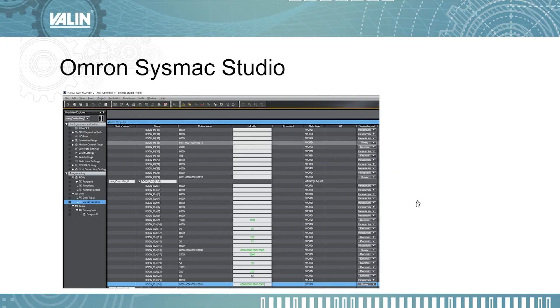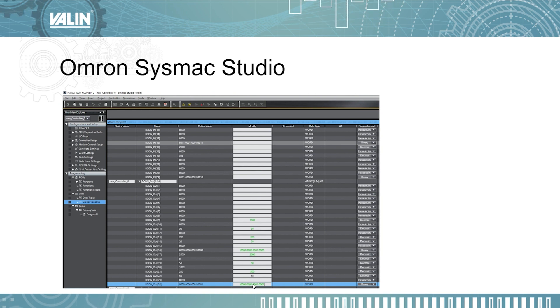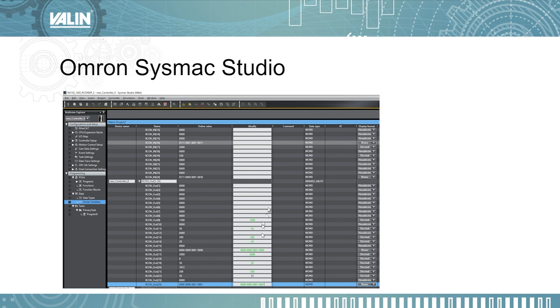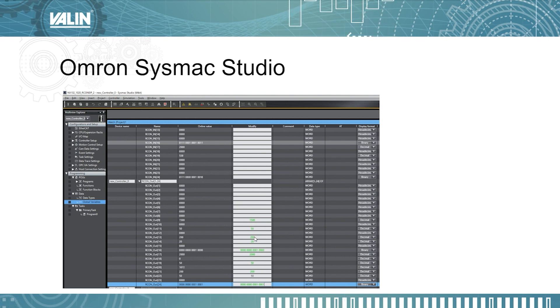This last slide shows basically all the bits we've been talking about: the registered control bits including the start bit, reset bit, jog forward, jog backward, and the data words for speed, position width, and also the actual position feedback — these apply to axis two and axis one respectively. That's how to set up Ethernet IP to communicate the IAI Archon Ethernet IP Gateway to an Omron NX-series PLC using the Parameter Configuration Tool. If you have any questions, please feel free to call us at the number below. Thank you for watching.